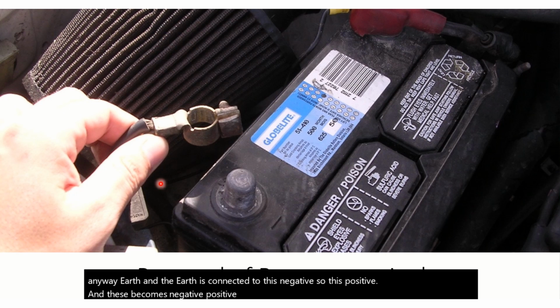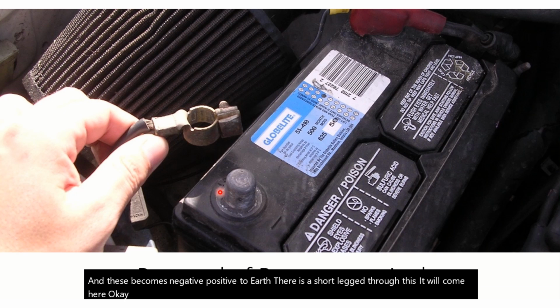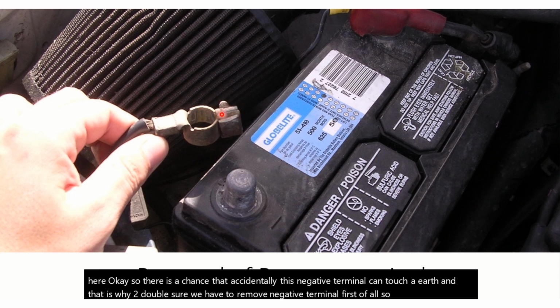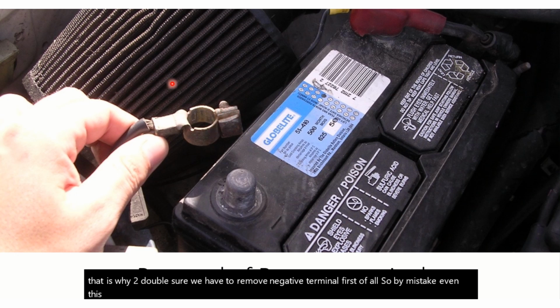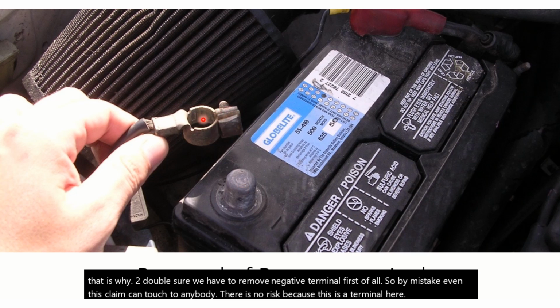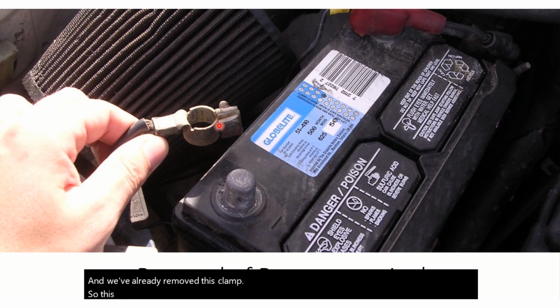There is a short circuit through this, it will come here. Okay, so there is a chance that accidentally this negative terminal can touch the earth, and that is why, to be doubly sure, we have to remove the negative terminal first of all. So even if by mistake this clamp touches any body, there is no risk, because this is a terminal here and we have already removed this clamp. So this is the reason that every time during battery maintenance the negative terminal has to be removed before we carry out any further maintenance.